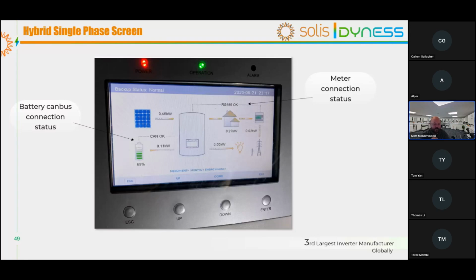First one on the left-hand side is CAN OK. Sometimes you might see CAN null, which means that the cable's not plugged in properly, so that CAN port is not connected to the BMS. Certain batteries have different CAN cables, so the pins are swapped at one side from the other. On the cable, you might see it says battery side, and on the other side, inverter side. That's hugely important. So make sure you've A, got the right cable for Dyness, and B, plugged it in the right way around. And that's what you'd see if you had CAN issues.